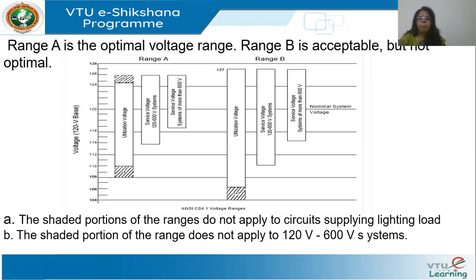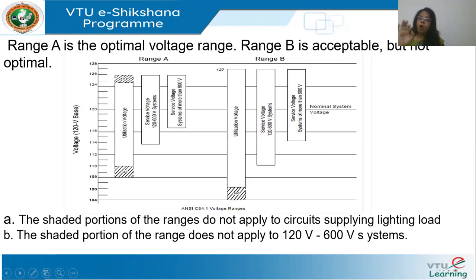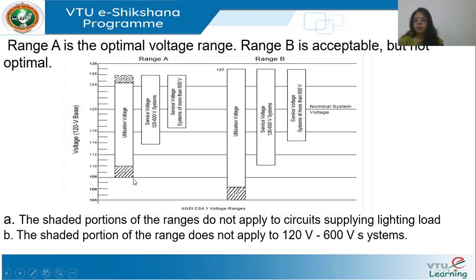Range A is optimal. We have the utilization voltage and the service voltage that can be guaranteed, including for systems where input is more than 600 volts. The standard does not guarantee 120 volts all the time — it allows the utility to permit the voltage to go up to 128 or down to 108.